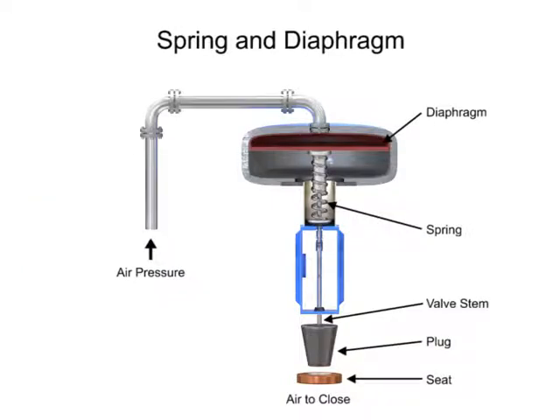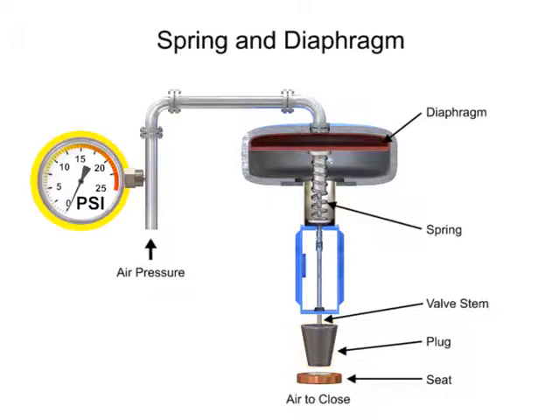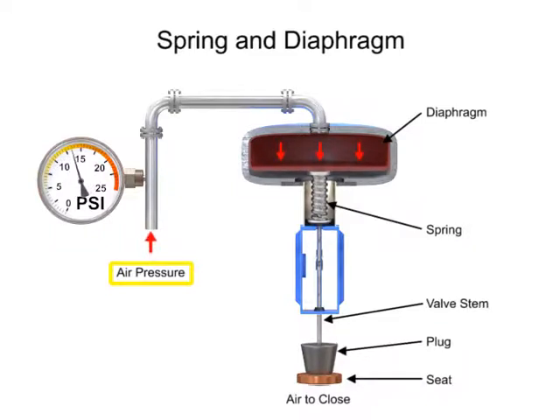The spring and diaphragm actuator uses a spring and a diaphragm to move the valve stem and plug. A 15 PSI pneumatic signal enters the housing at the top of the actuator. As pressure is exerted on the diaphragm, a downward force is applied against the spring which moves the restrictor. The diaphragm moves until it creates an equal but opposing force against the spring, at which time the motion stops as the plug meets the valve seat.